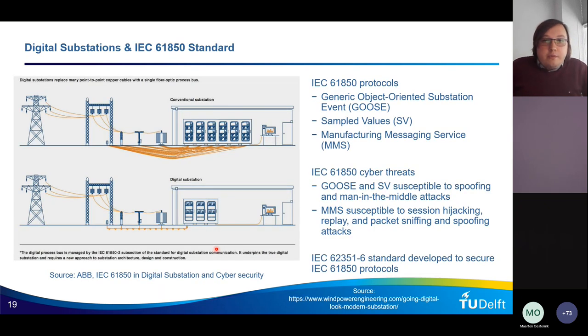Now, in order to go a little bit more in depth and have a better understanding of how we can investigate their impact, and also what we can do to mitigate, I would first like to introduce the digital substation concept and a communication standard that is used for digital substations, which is IEC 61850.